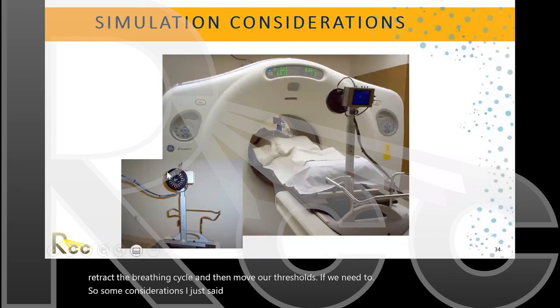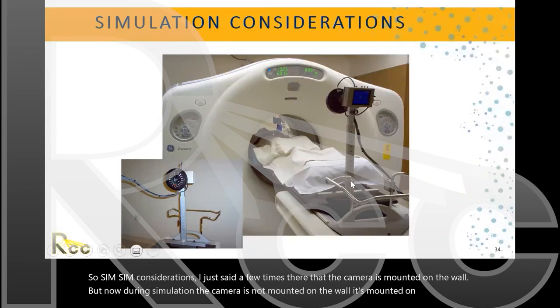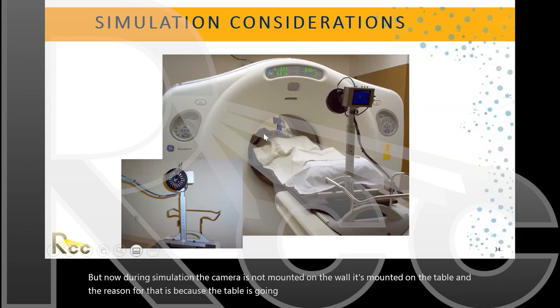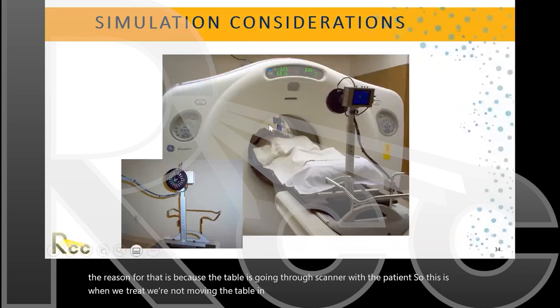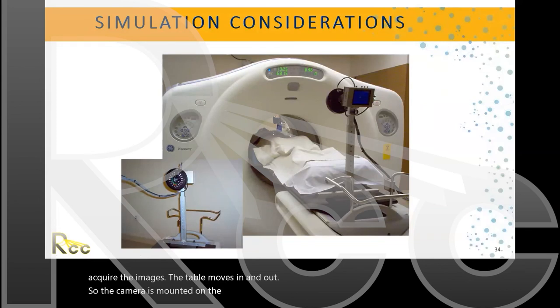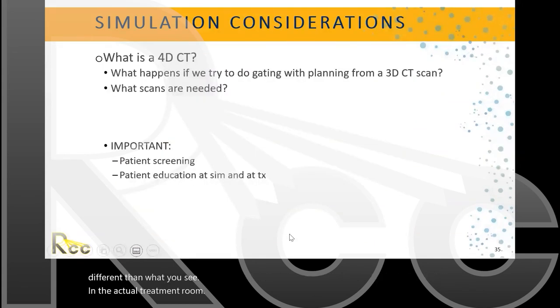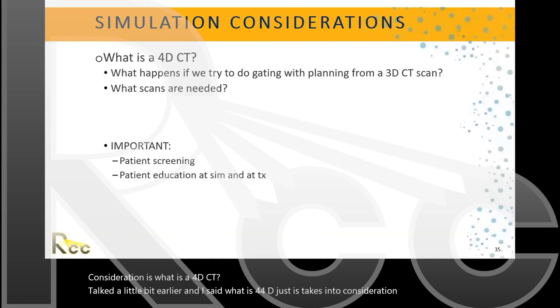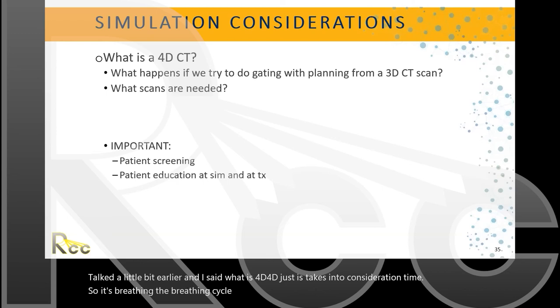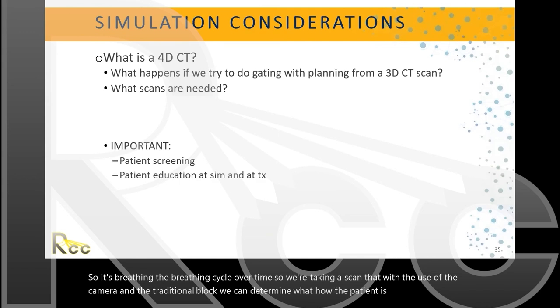During simulation, the camera is mounted on the table rather than on the wall, because the table moves in and out through the scanner with the patient. During treatment we're not moving the table in and out, but during simulation we are moving the table to acquire images. This is a key difference between what you see in the treatment room and what you see at simulation.